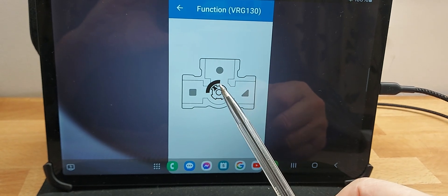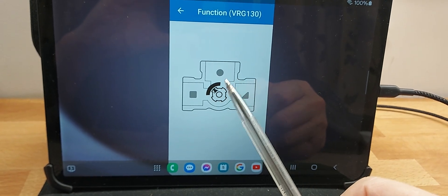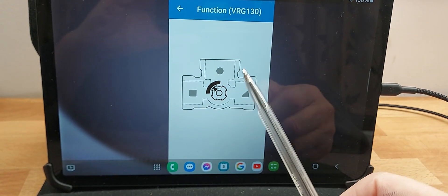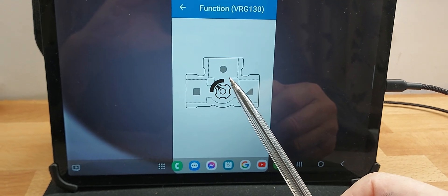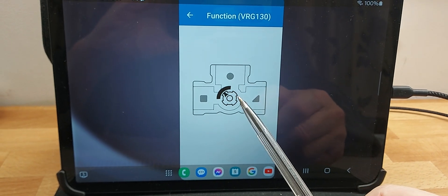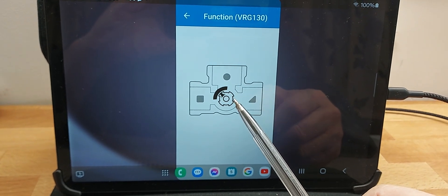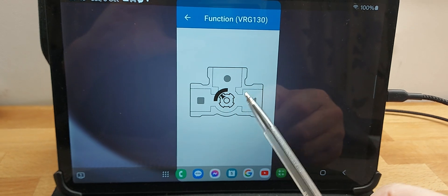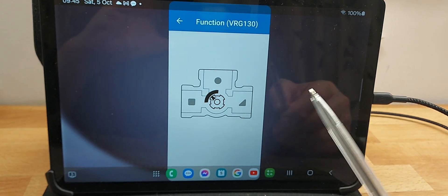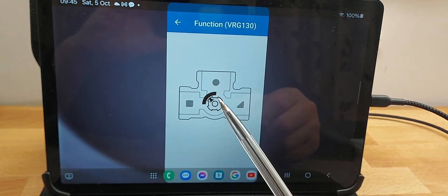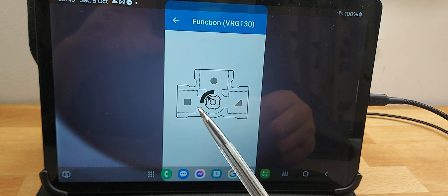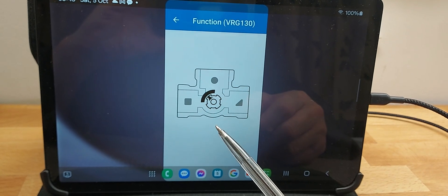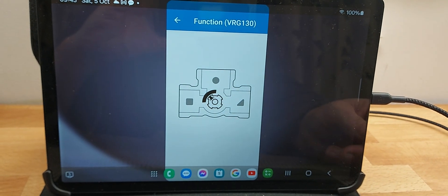This has to be the correct size to allow the correct flow rate to go through here. The rule for that is that the resistance to flow through this circuit, or Delta P in the load circuit, should be equal to the pressure loss through these apertures for the mixing to take place.